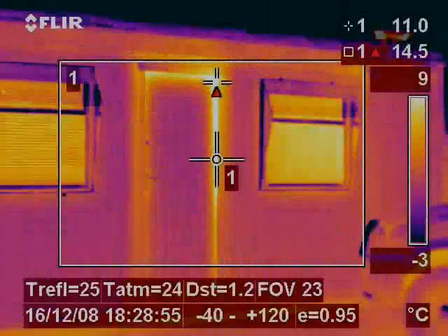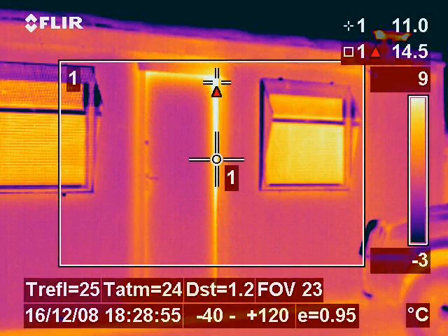This image was taken of a porta-cabin type office building. We were looking for any signs of heat escaping from the building. A damaged door frame showed a big heat loss.